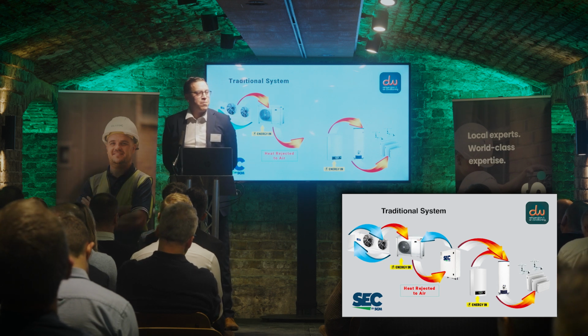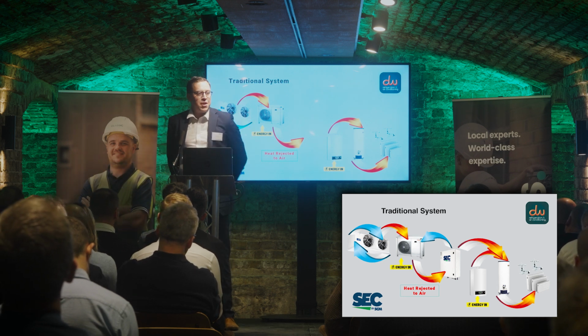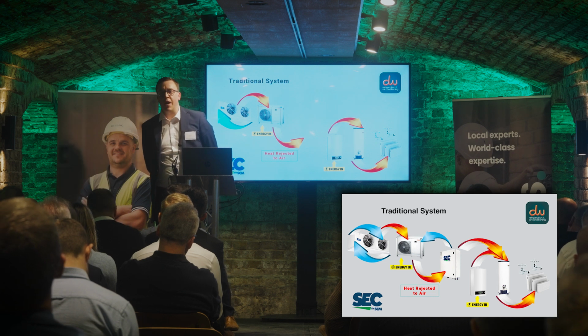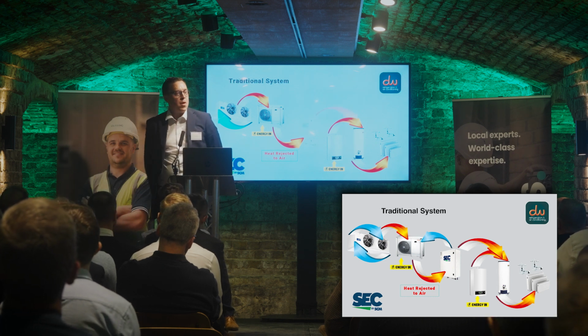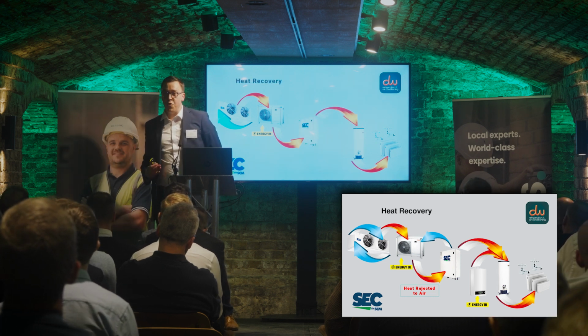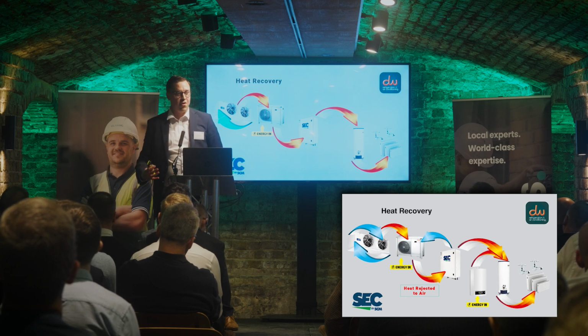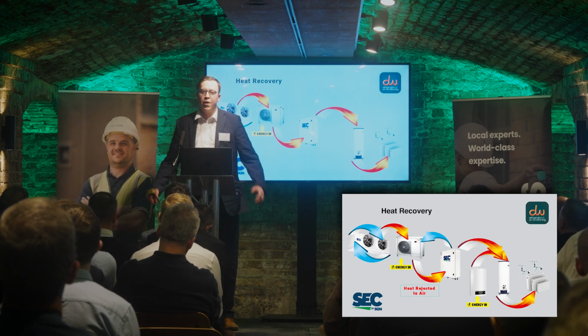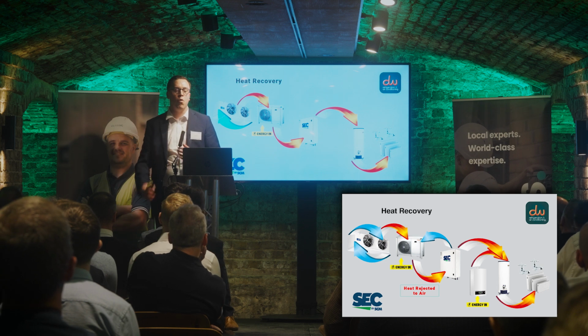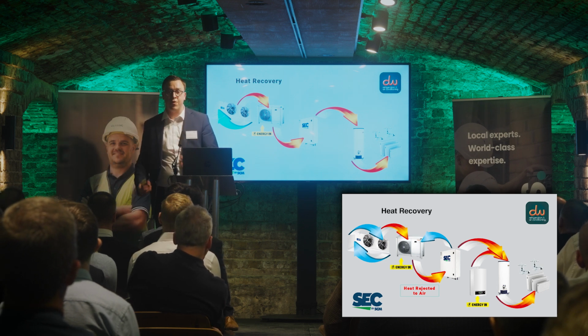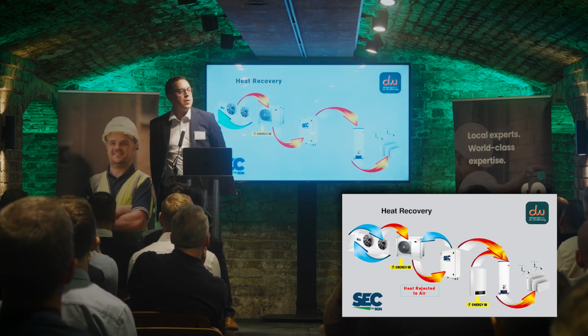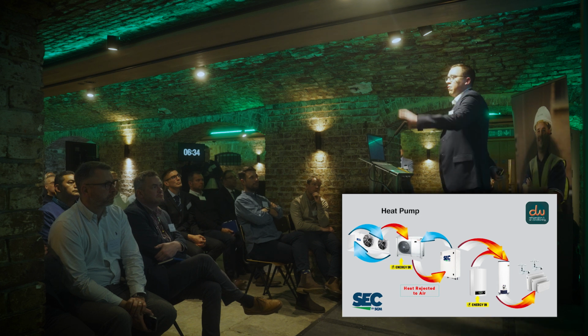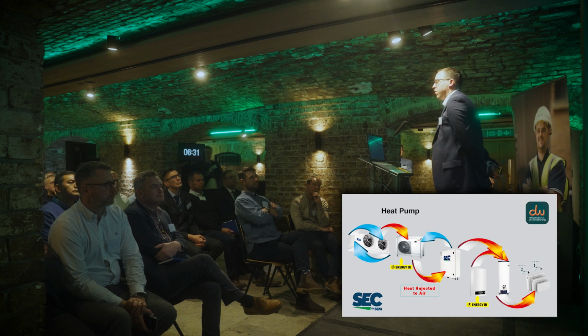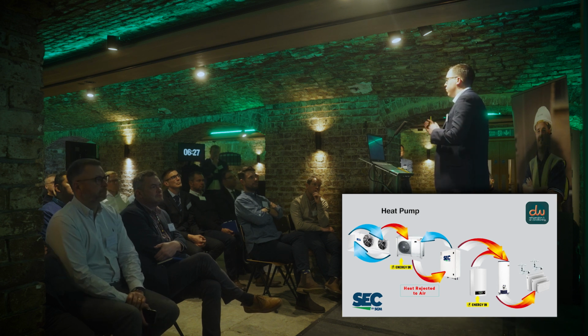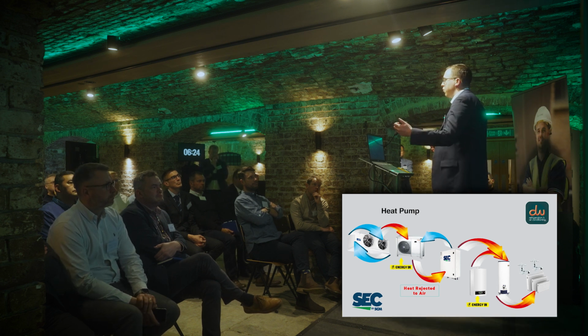So a traditional system, as I say, you'll have the cooling side and an energy input, and then you'll have your boiler or electric immersion with an energy input. SEC can remove that energy input in its entirety on the hot water side, or it can be the main source of hot water being delivered, with a gas boiler or electric immersion just backing it up or topping it up. In heat pump mode, that's when, as I've talked about, the cooling side is satisfied, but there's still a need for the hot water, and the PLC really is understanding the inputs from the heating and the cooling side.